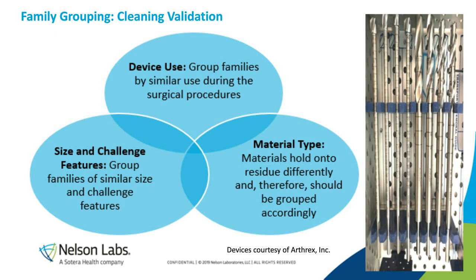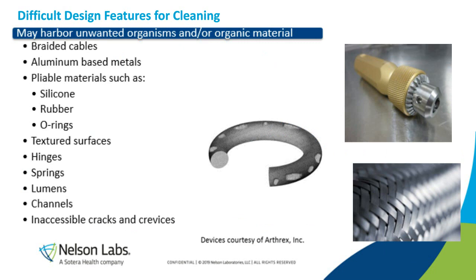And just to expand on these size and challenge features, we look at these that may be difficult for cleaning and may harbor organisms and organic material. And these parts of devices include braided cables, pliable materials, textured surfaces, hinges, springs, lumens, specifically dead-ended lumens, and inaccessible areas of the device that are difficult to reach for cleaning.